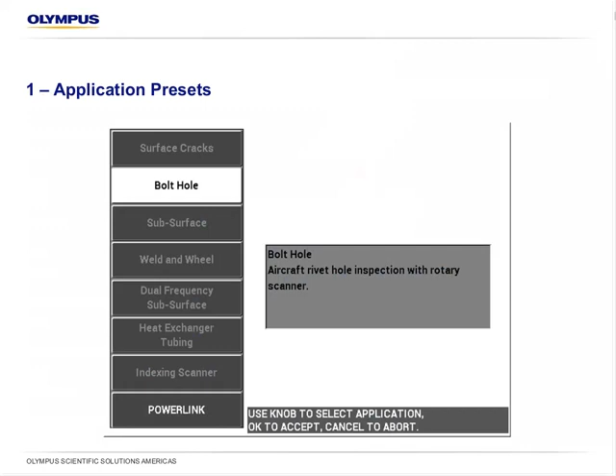It's really to display the key features, the real improvements that made this solution an improvement for fastener hole inspection. So number one, application presets. When you power up the NORTEC the first time, or on demand, you can access this menu. It's called application presets. Those are basically factory presets that set all kinds of settings for all the common eddy current applications, including fastener hole inspection. It saves the user from a lot of steps because pretty much everything is preset, and it also allows you to instantly configure for fastener hole inspection.